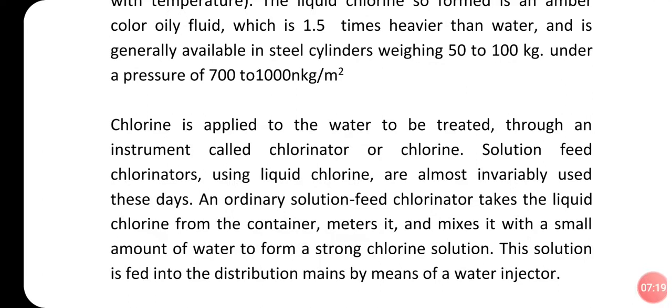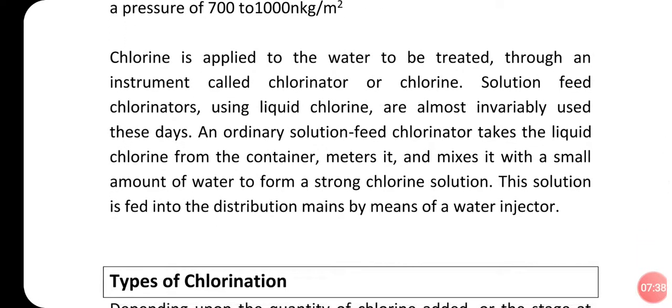So solution feed chlorinators using liquid chlorine are almost invariably used these days. An ordinary solution feed chlorinator takes the liquid chlorine from the container, meters it, and mixes it with a small amount of water to form a strong chlorine solution. So this is the procedure of how it is being done. So this solution is fed into the distribution by means of a water injector.